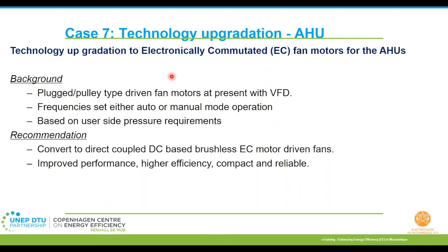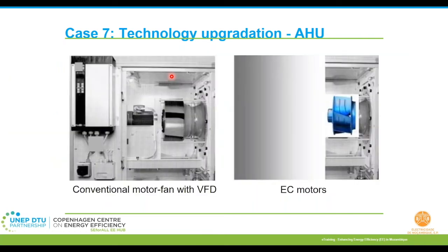The technology is nothing but DC-based brushless electronically commutated motor driven fans. These are actually much better in terms of performance. They give higher efficiency and they're compact and reliable. If you see the picture on the left, this is a complete setup of a VFD panel. You have a motor and then a blower or a fan for the AHU system. And if you see the EC motors, there's hardly this. That's it. It's compact and everything is more efficient. It's even more silent. There's hardly any noise that comes out.